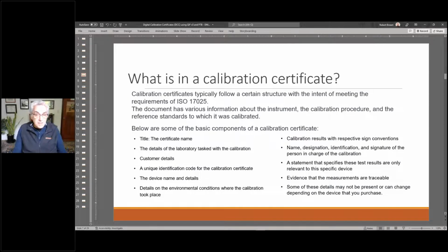Now, specifically, when we look at what is a calibration certificate, there are certain structures and content that are required to meet ISO 17025. Various information about the instrument, the calibration procedure, the calibrating organization, the reference standards that were used, the date, the as found, the adjusted. These are all aspects of a calibration certificate. So you have the name, the lab, customer details, address information, environmental conditions, temperature, humidity, pressure, certainly the values themselves, and then a statement. And these are, again, traceable.